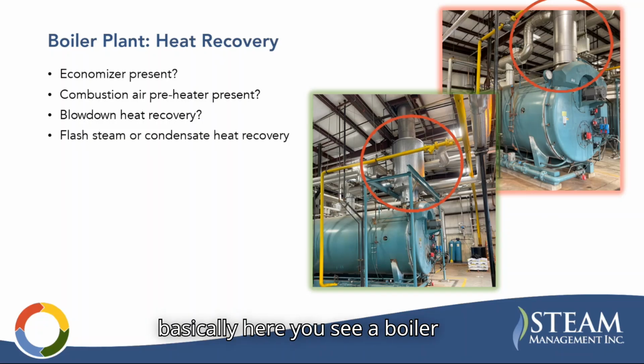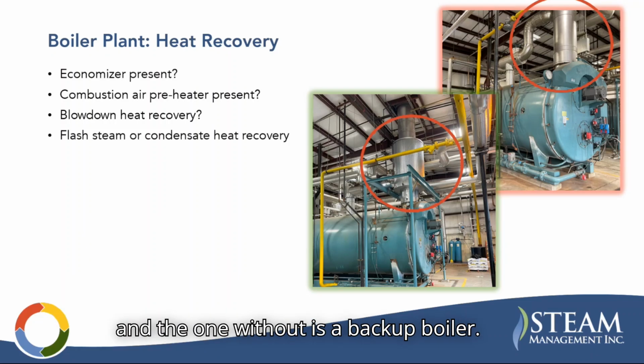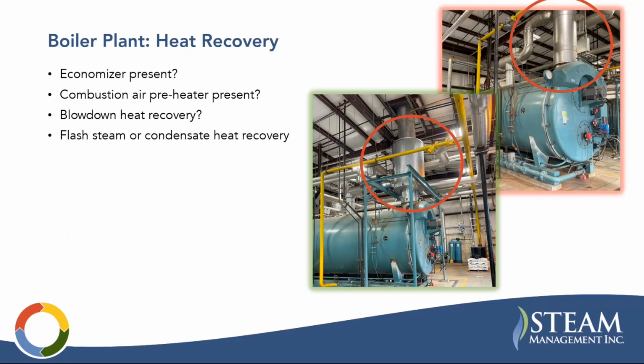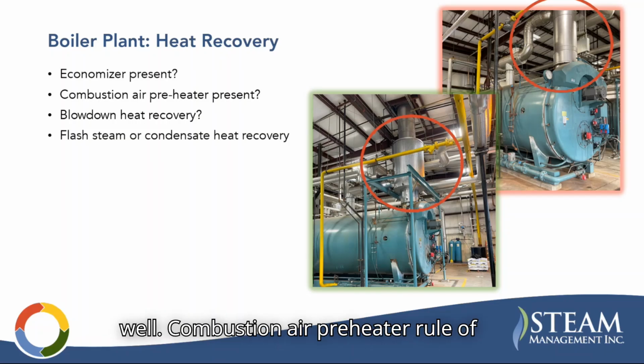So here you see a boiler with a feed water economizer, and here's one without. And these are actually in the same boiler room. As you can imagine, the one with the feed water economizer is the primary boiler, and the one without is a backup boiler. That's something to look at with these opportunities, because I often get excited when I see that there isn't an economizer, but a lot of times there's a reason for that. Like it's got low run hours, or whatever. It wasn't worth investing in, and maybe it's still not. But they also often can be an opportunity as well.